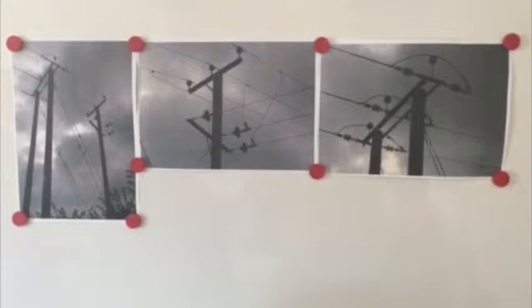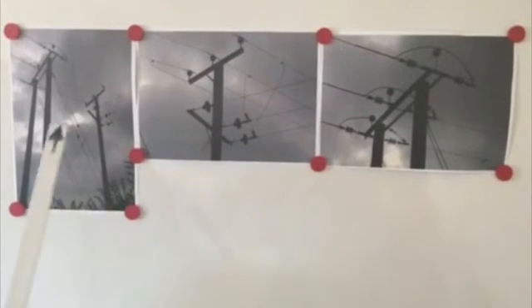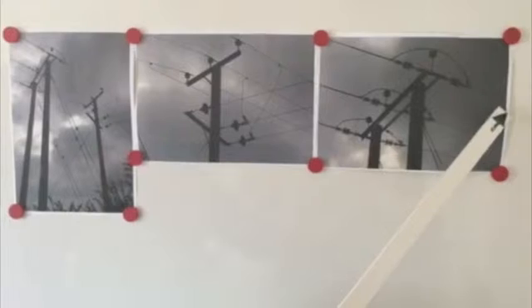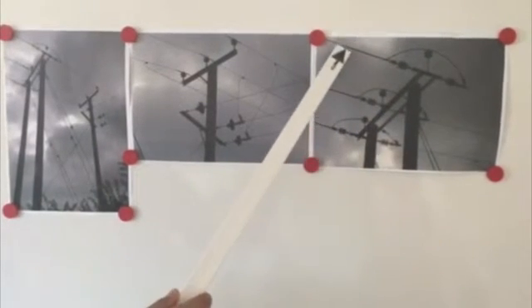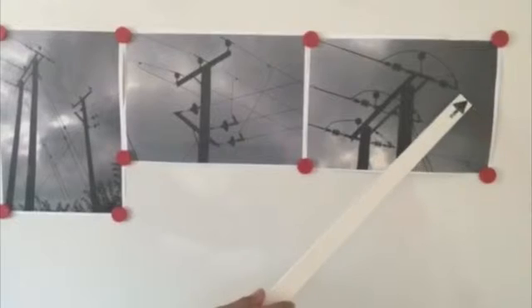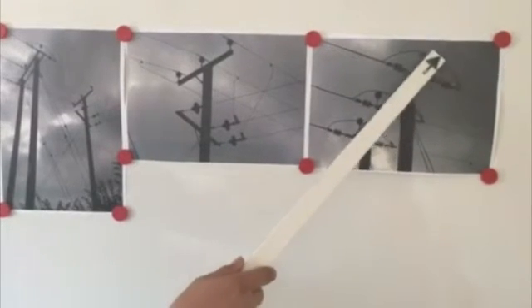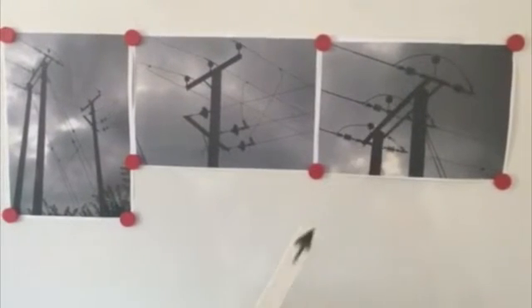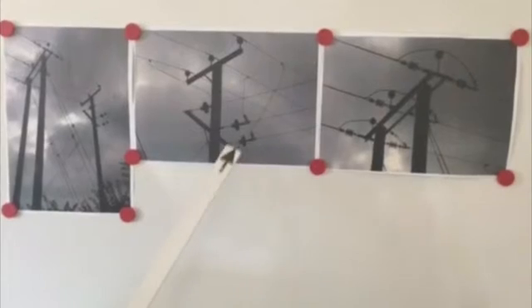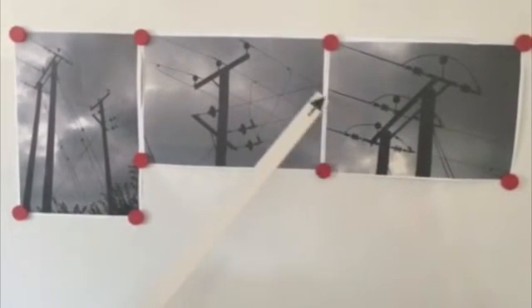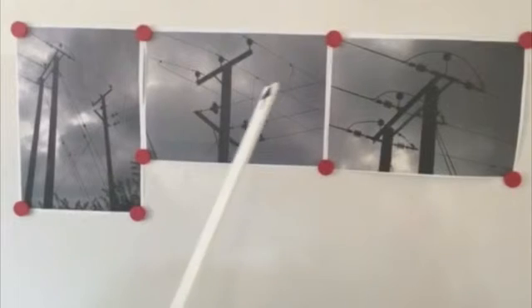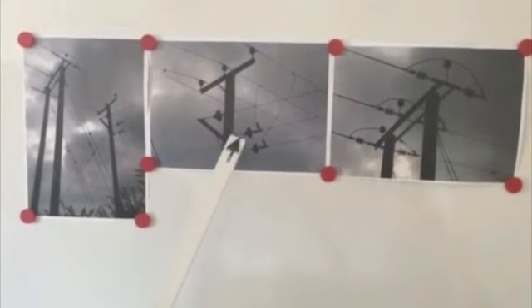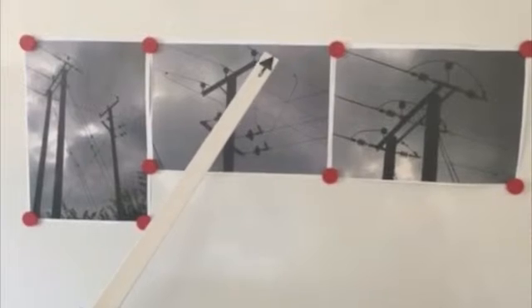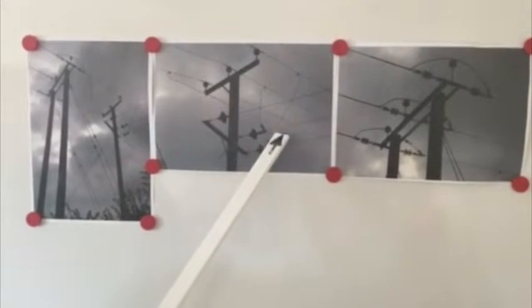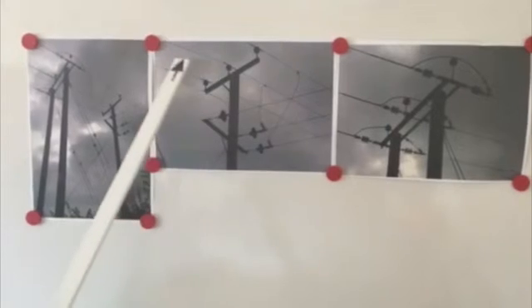Here we have a series of pictures showing different line connections. The picture on the right shows a line coming in from the right and going out on the left. In order to connect the electricity from one point to another, we use a loop connection. The loop is insulated at the top via the pin insulator. Moving on to the second picture, we have a line coming in from the right and then a cross section going out in a different direction. In order for the electricity again to be connected from one line to the other, we use a series of wires. They again are called loop connections.